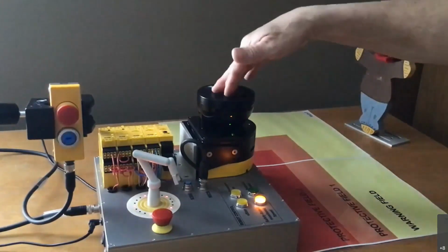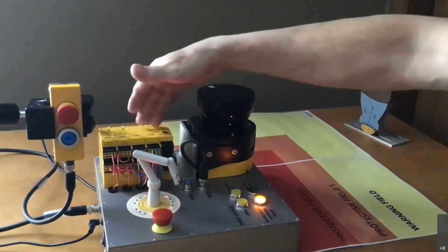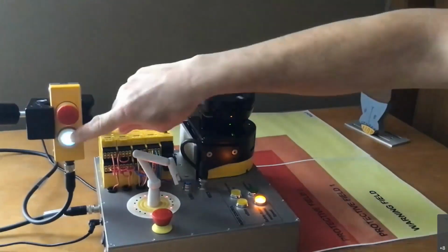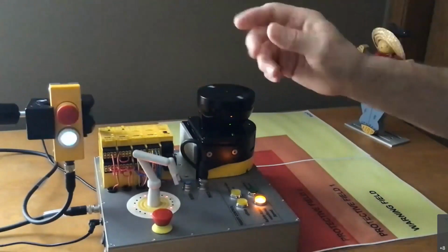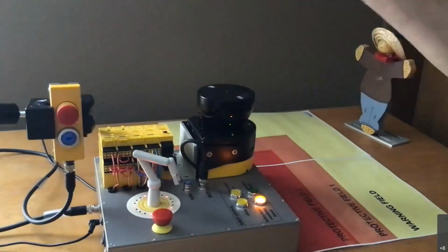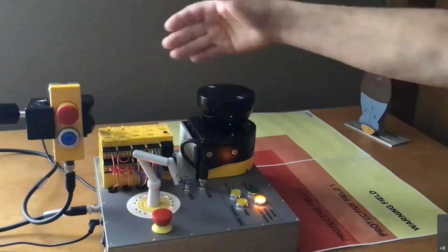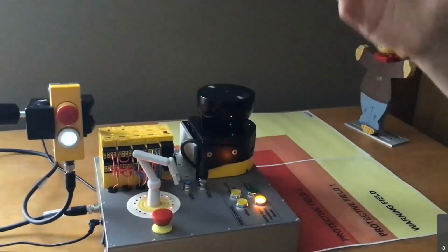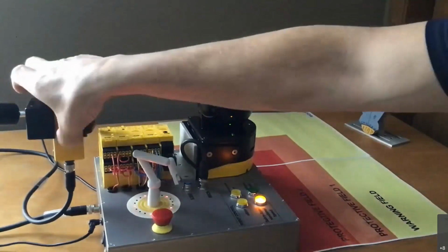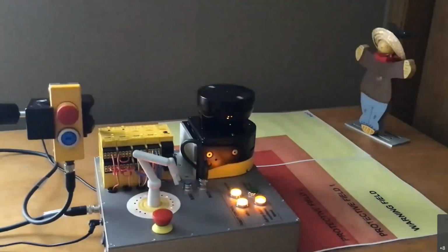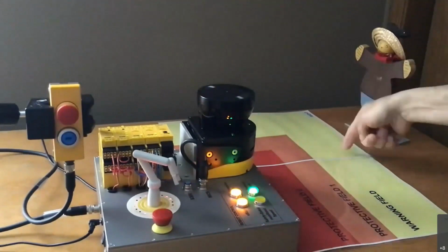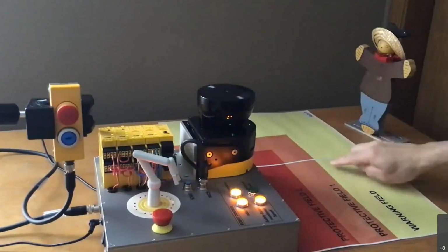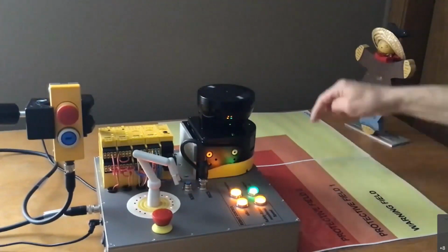So it includes a safety laser scanner, safety controls, whichever controls would be applicable for your robot. You normally have the e-stop and reset buttons incorporated in. It has the program for the laser scanner and the program for the safety logic, which is specific to your robot. This is called sBot Speed because it has custom function blocks built in. So if you notice here, I have a yellow zone, which is my warning zone, which is my slowdown zone. I've got a protective field 1, and I've got a protective field 2.